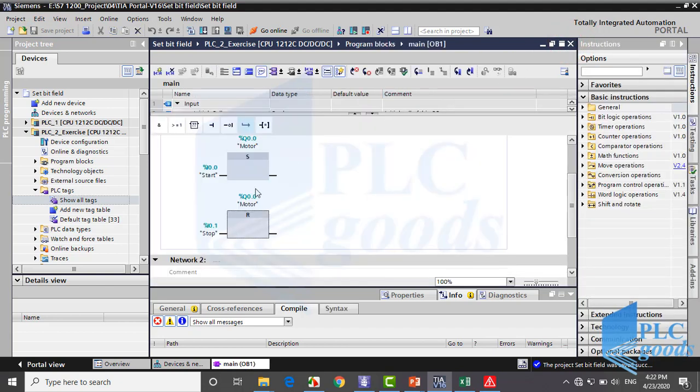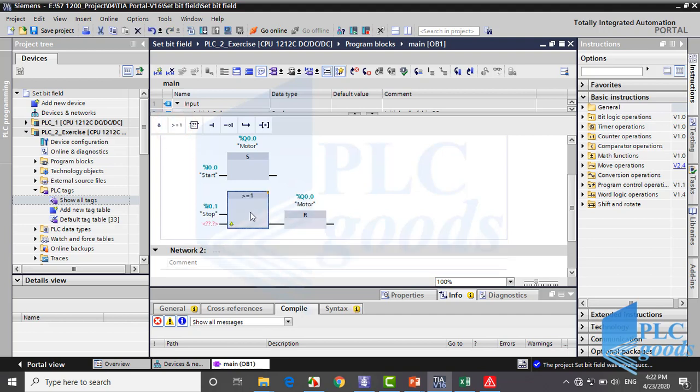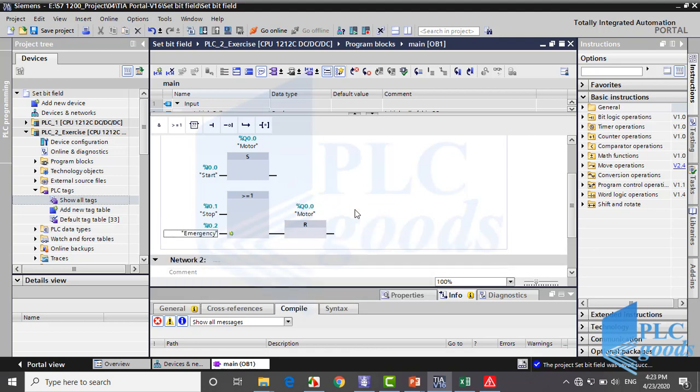As you see, the I0.0 address sets motor to on, and I0.1 contact resets it to off. But in this project we have the emergency push button beside stop, which resets the motor to off. Listen again: stop or emergency turn the motor off. So we need OR logic. Well I click here, and then insert an OR block, now insert emergency address or its tag here.